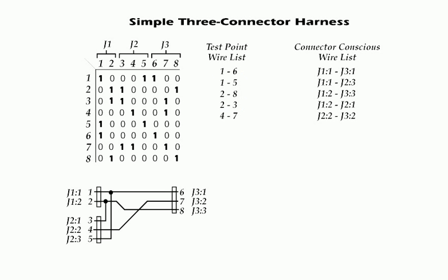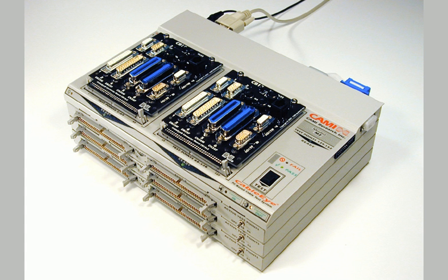Practical wire harnesses have dozens of connectors, some of them quite large. For applications requiring more than 128 test points, expansion modules may be added to CableEye to provide as many test points as you need. The expanded system you see here provides 512 test points. The top unit has two 64-pin headers, which you may access by removing the plug-in boards. 6 more 64-pin headers are available below.